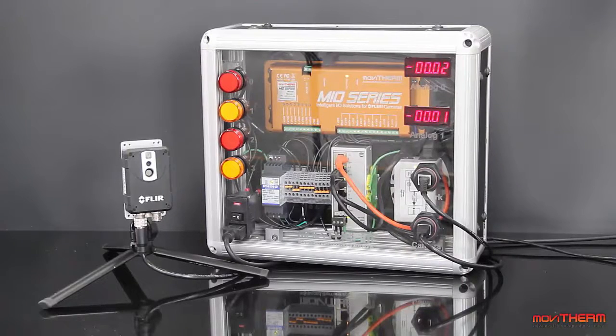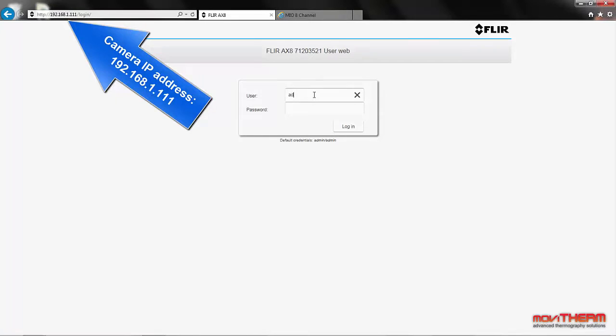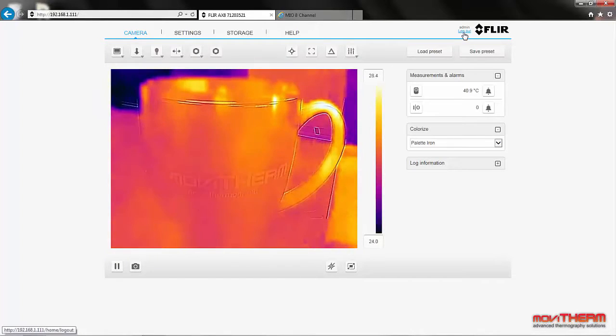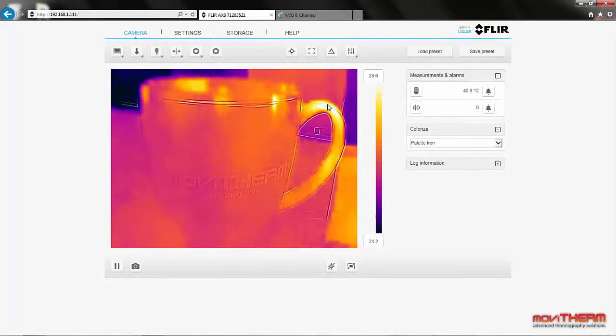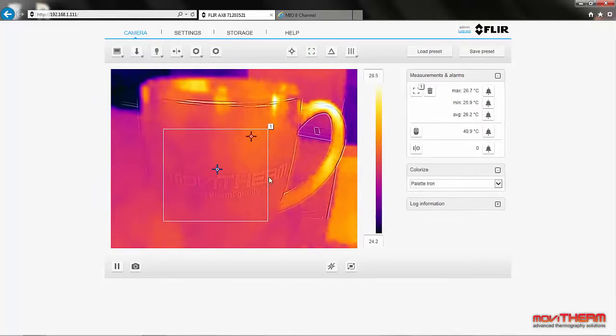We will also use a FLIR AX8 camera for the video, so let's start by configuring the camera. The IP address for the camera is 192.168.1.111, so we will type that address into the browser's address bar and log into the AX8 camera. Here's a live thermal image from the camera. We're going to put some hot water into this cup and watch the temperature change. Let's set up a region of interest so we can display and track the temperature changes. We click on the box icon to create the box and then drag the edges to define the region. Notice the maximum temperature in the region is currently around 26.7 degrees Celsius.